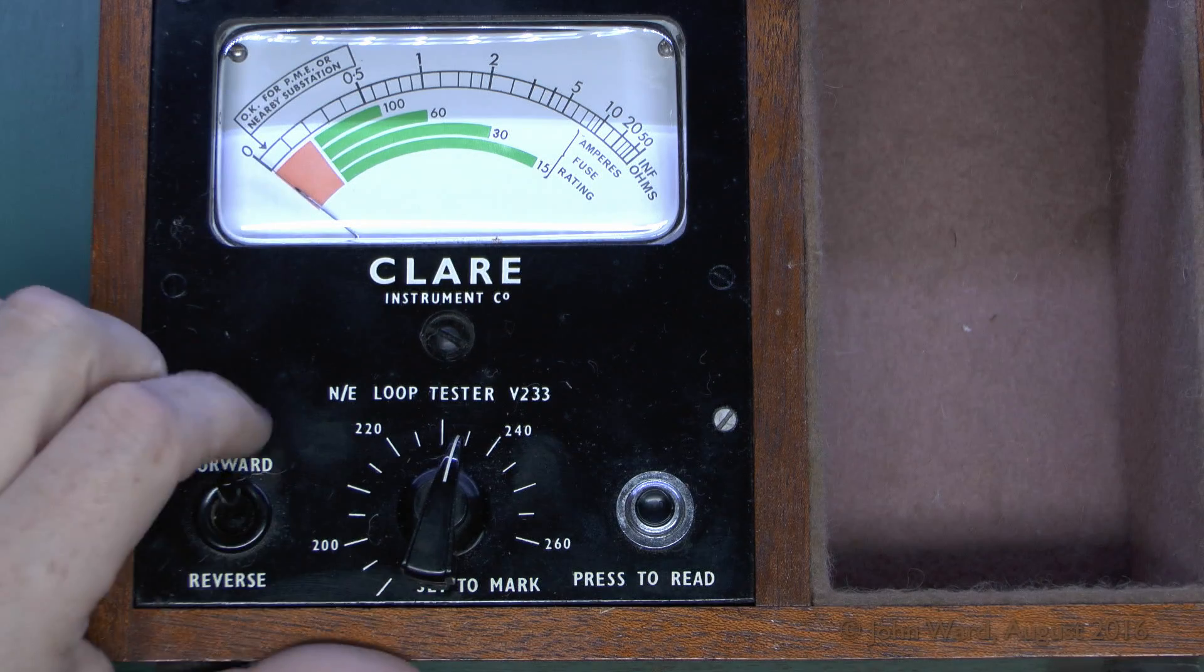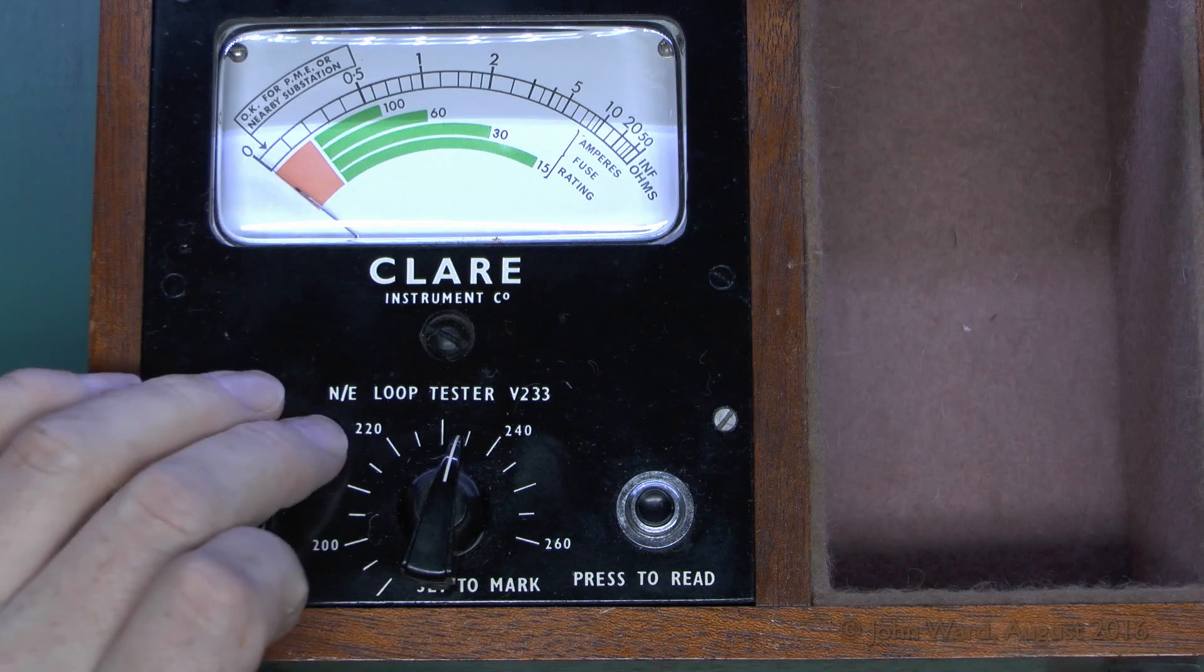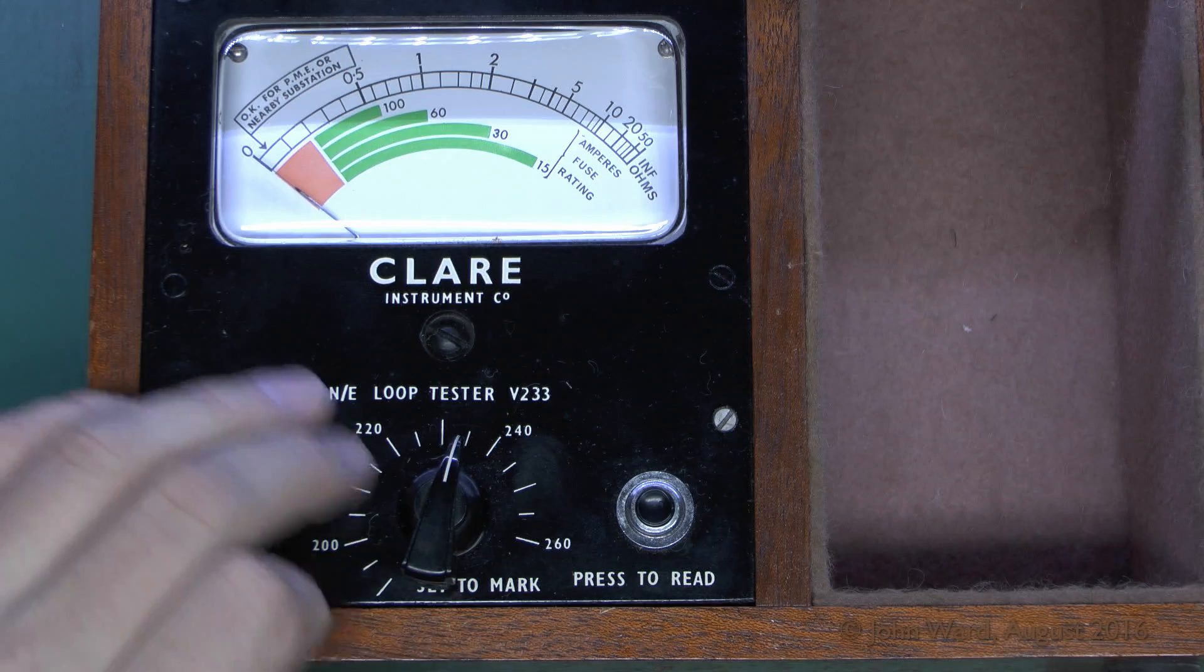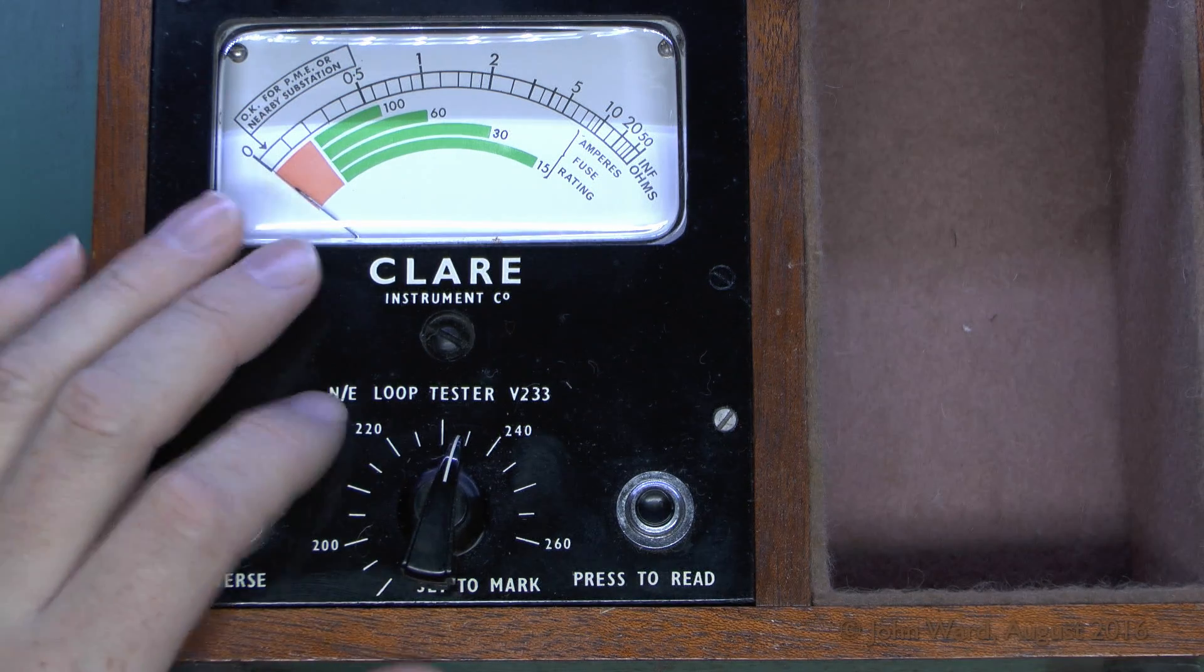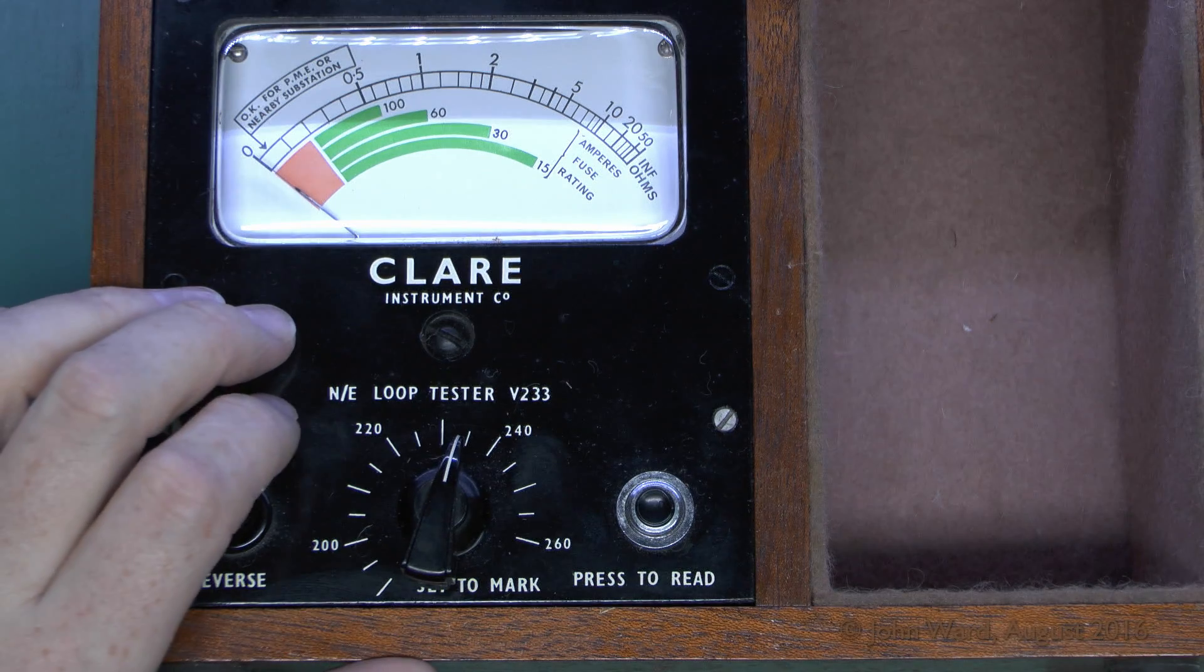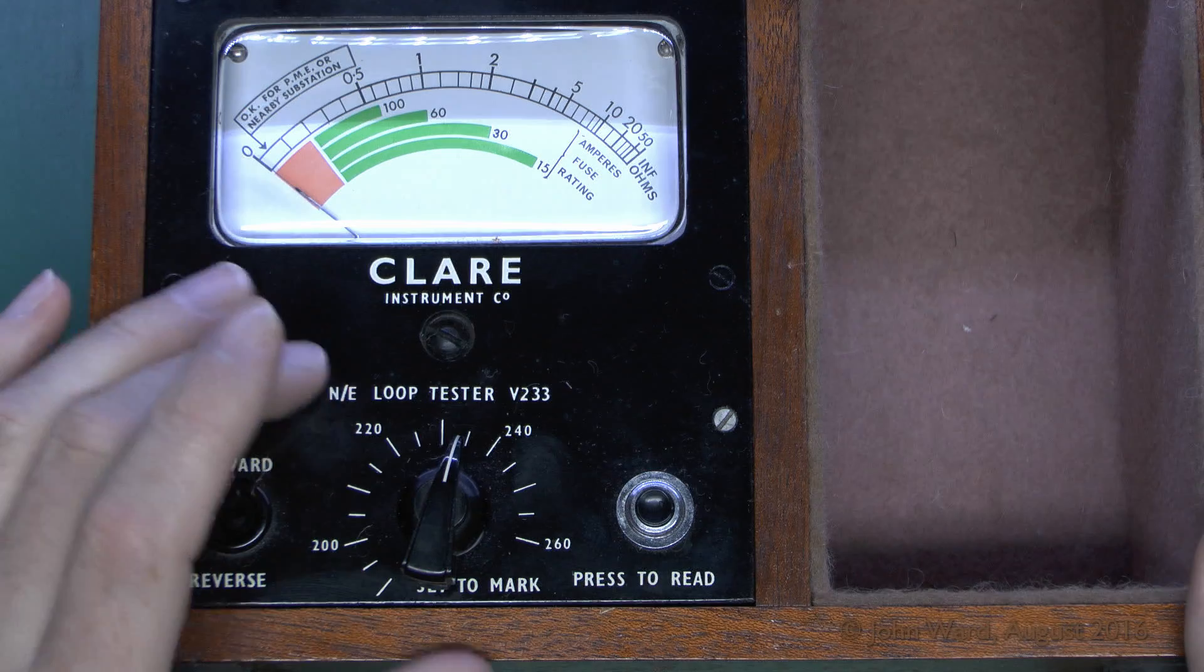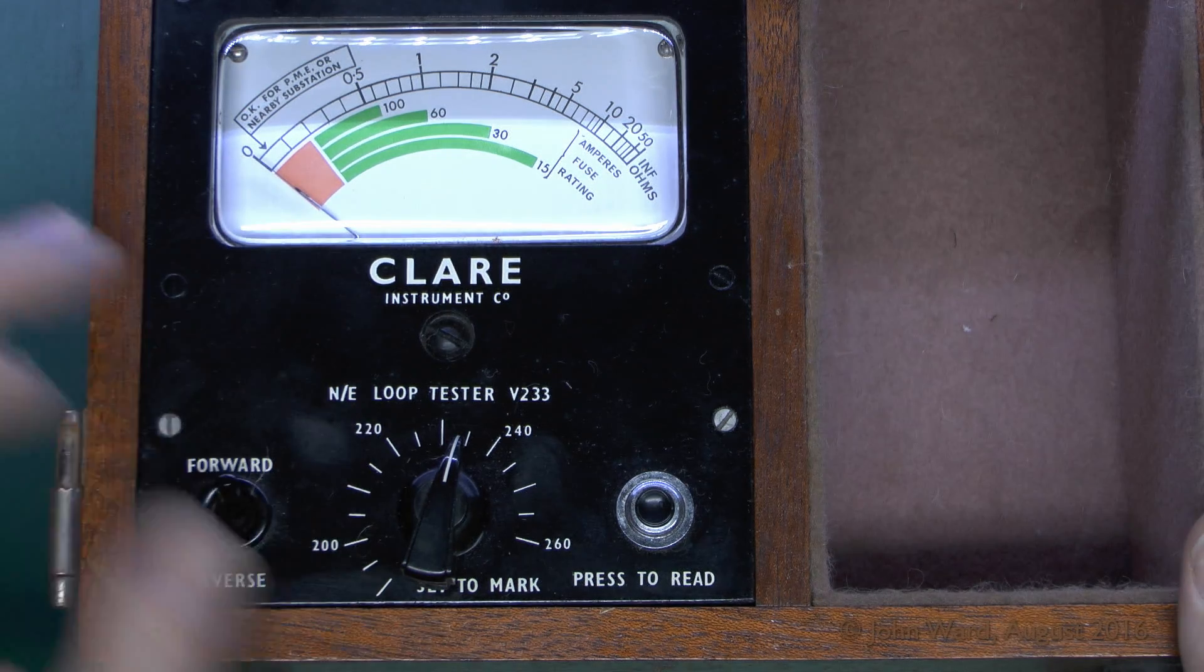So essentially it's putting a voltage there, and it's actually then measuring the current which flows. This is a test which you wouldn't normally do these days, mainly because the newer equipment is a line earth loop tester, or in some cases a line neutral one. For those you've got the mains power there already, and with those it's normally the case you're just applying a fixed resistance across that and measuring the voltage drop. But this one is somewhat more unusual.